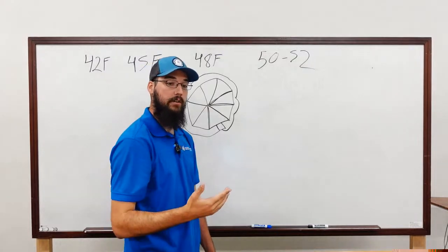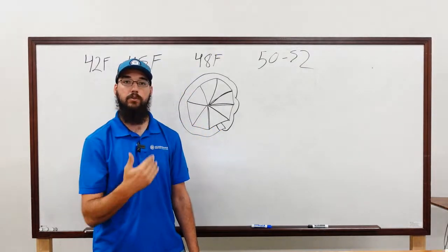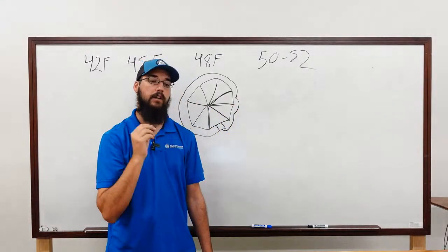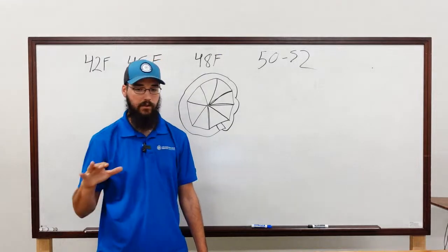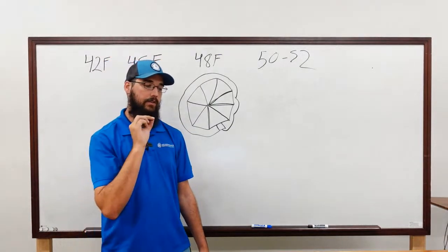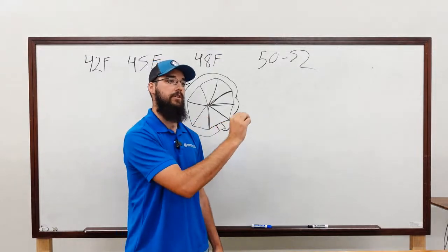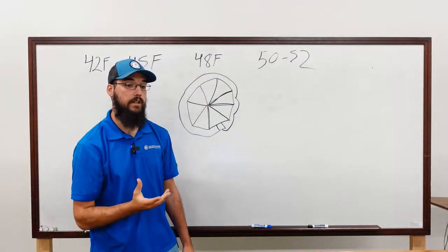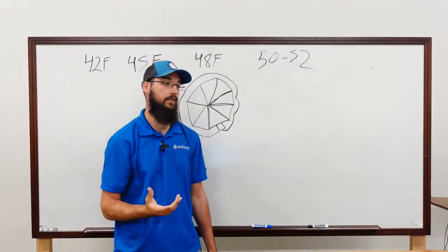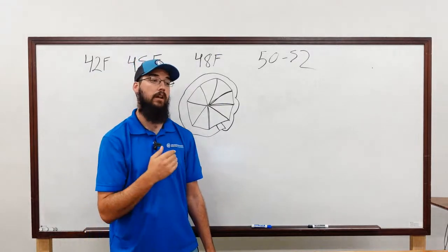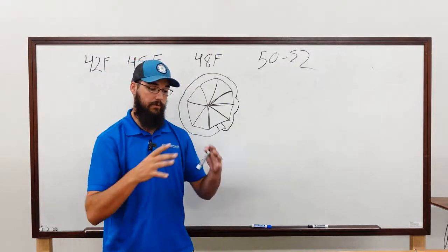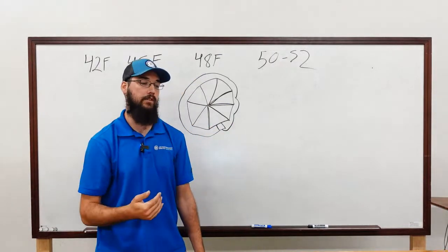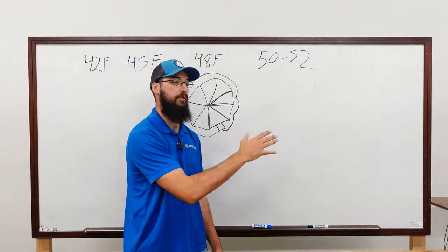And what can happen, just because you start cycling a low suction pressure limit or low pressure limiter, right? That doesn't mean there's something wrong at all. What that means is the machine is loading a little faster than the refrigerant circuit can keep up. This is really common on screw machines. I see this all the time with screws, but I've seen centrifugals do it too, where given the right conditions, that compressor will load faster than the metering devices are able to supply it refrigerant.